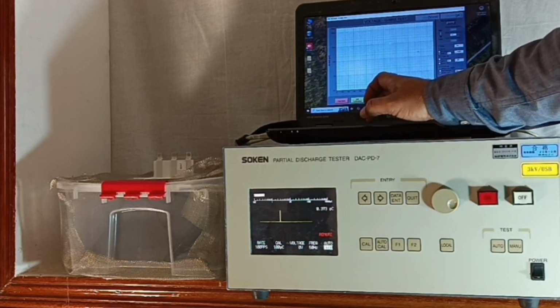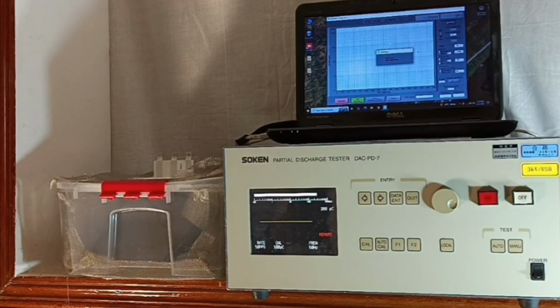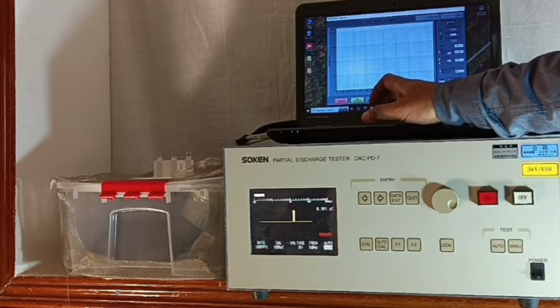So now, to start with, first we are required to calibrate the meter for the scale to fix the gain of the amplifier. So we have selected 100 pC as the calibration pulse. So now you can see automatically it has gone to 100 pC and the calibration is complete. To start the measurement, we have to say test start. The voltage is applied. There is an interlock also which is provided. If the door switch is open, the voltage will go to 0. Now we can see the voltage is increasing.